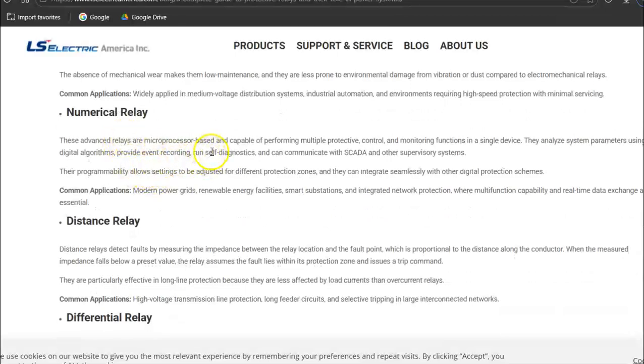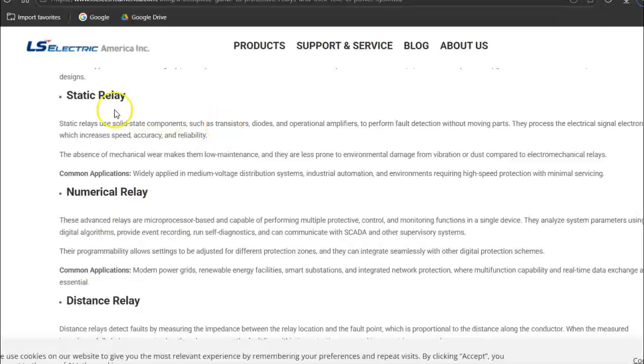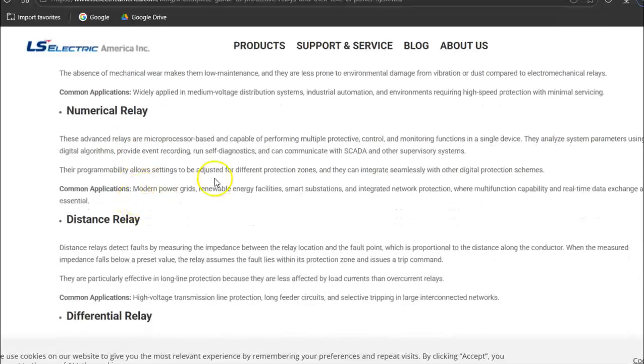Numerical relays are advanced, microprocessor-based relays. Static relays are more like an analog value. You have amplifiers in there, and you can set the gain and set trip levels, and it will trip. Numerical is digital. It's basically a PLC, a very precise function. They can do all kinds of things. They can analyze system parameters using digital algorithms. They can record data like a data recorder, run self-diagnostics, and communicate with SCADA, HMIs, and other supervisory systems. So it is a full, powerful machine.